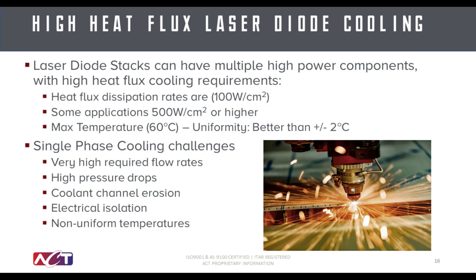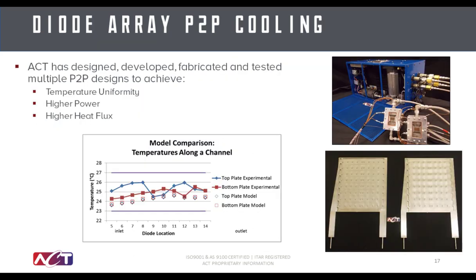One application that we've spoken about is related to high heat flux cooling of laser diode applications. One such application would be laser cutting materials, where the high-powered lasers must maintain a constant temperature over the course of their operation to maintain the proper wavelength of the laser. These laser diodes can have heat fluxes greater than 500 watts per centimeter squared, and often require uniformity across the various components of better than 2 degrees C. If a single-phase cooling system were to try and achieve this kind of performance, you'd require significantly high fluid flow rates, and you risk damaging your cold plates.